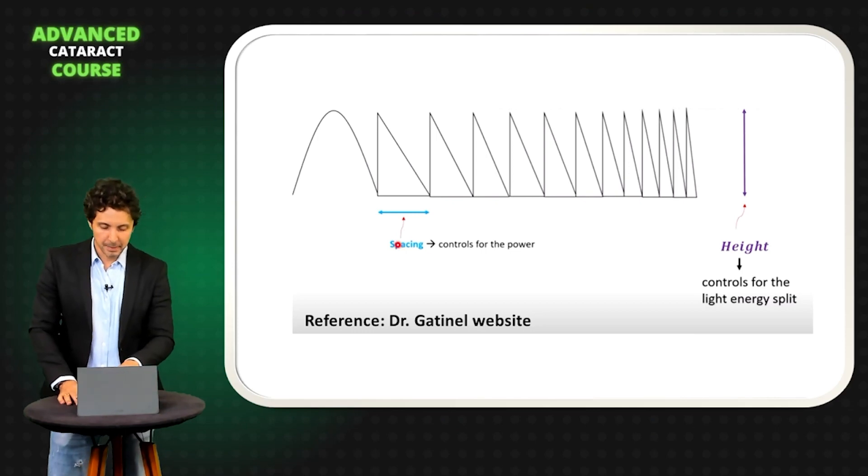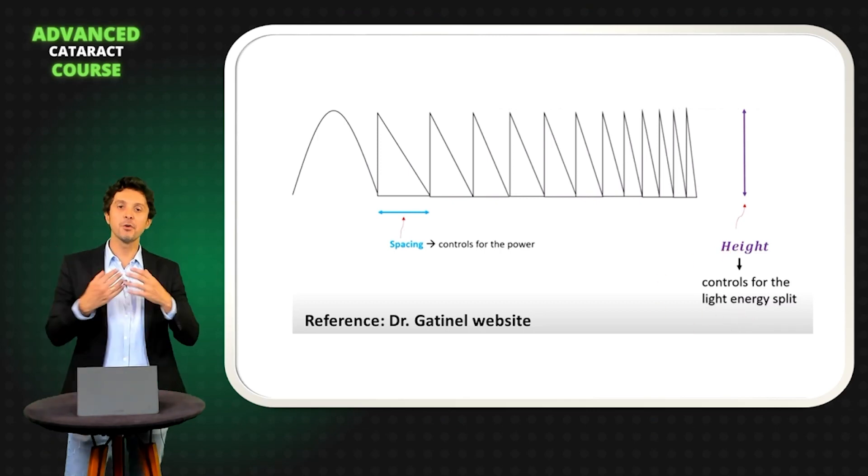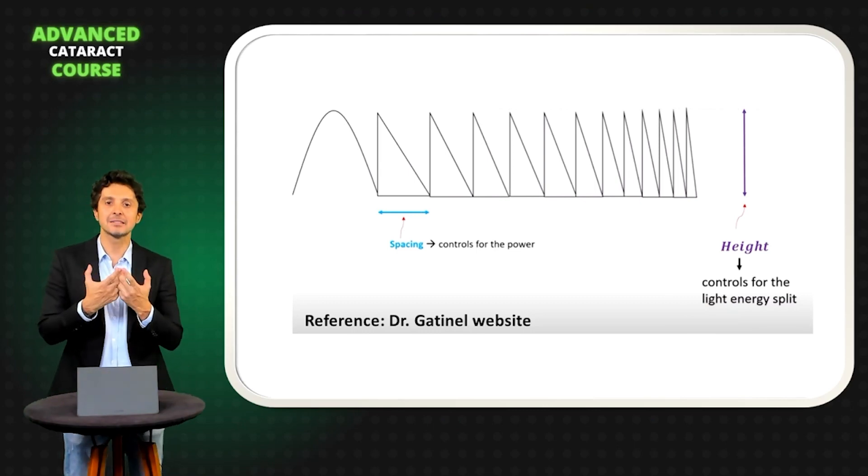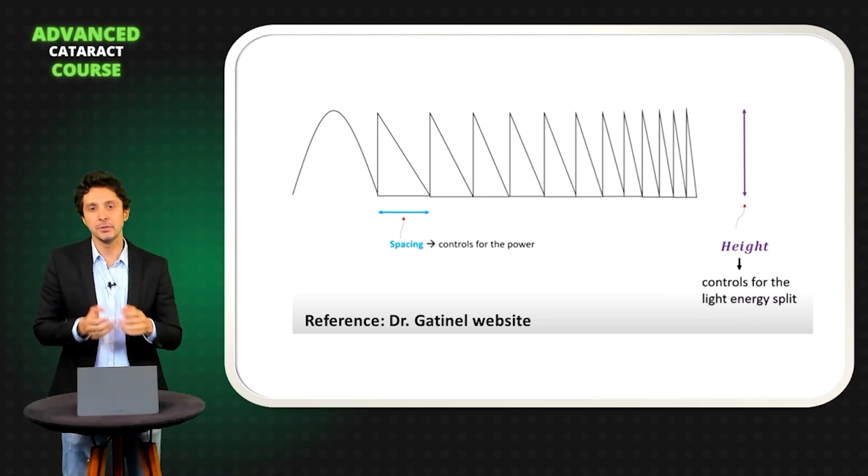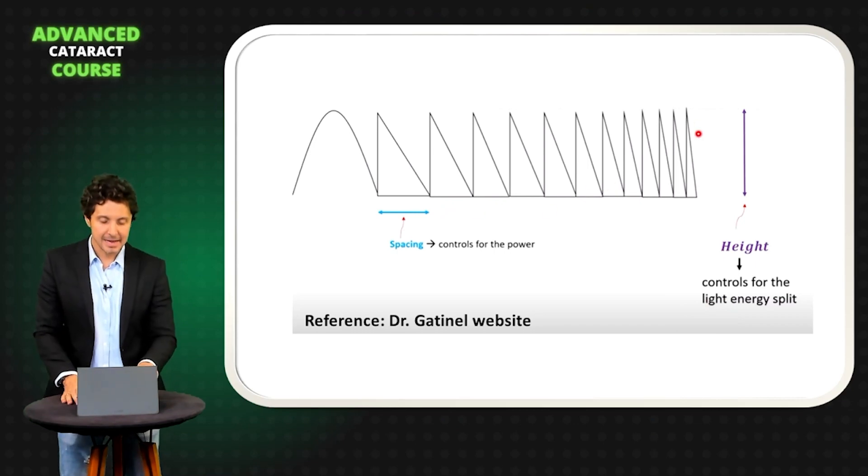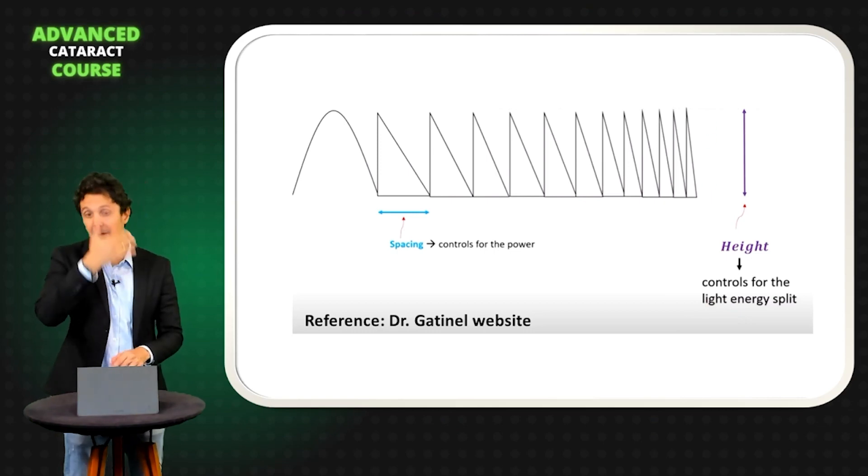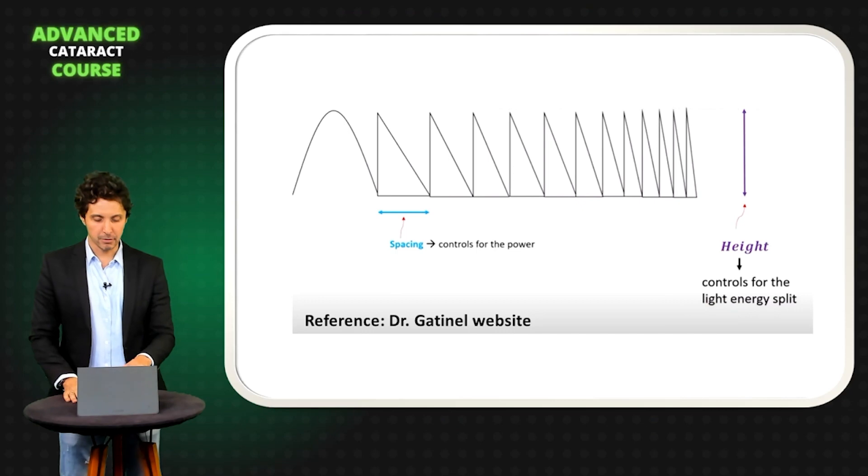You can observe spacing controls the power, but the height controls the light energy split. So if you want in your IOL less energy split, less night symptoms, less halos, you need to modify this height. This is the second rule to produce an amazing trifocal IOL.